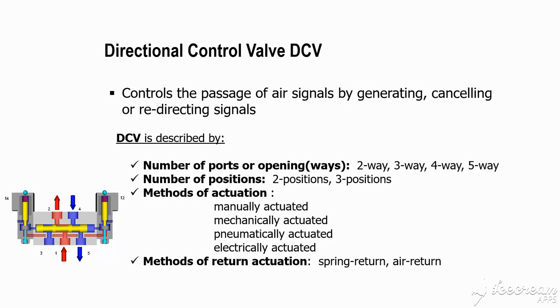Methods of activation: you can operate valves manually, mechanically using levers or switches, or pneumatically — where compressed air activates the valve and stopping the air returns it to normal position. This is called pneumatically activated or pilot operated. You can also use electrical actuators, which are widely used in electro-pneumatic systems. The return to normal position can be by spring return or by applying air to the other side.